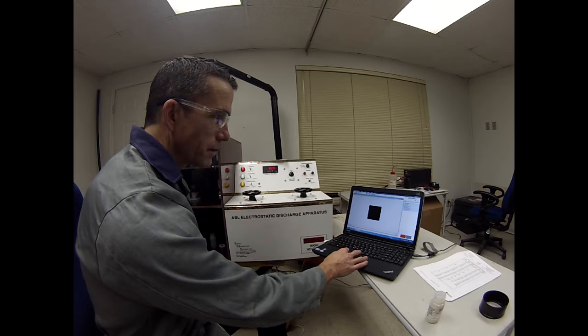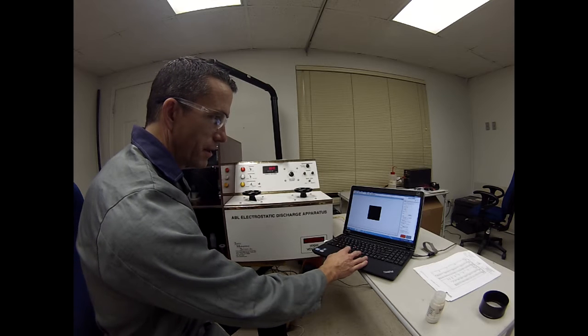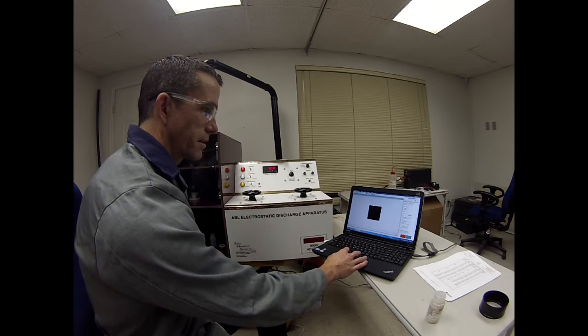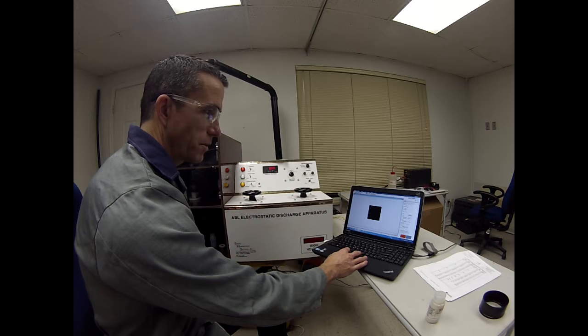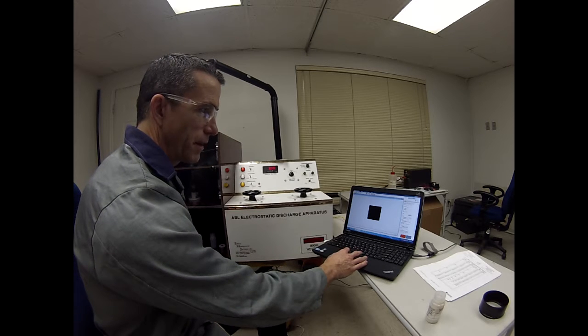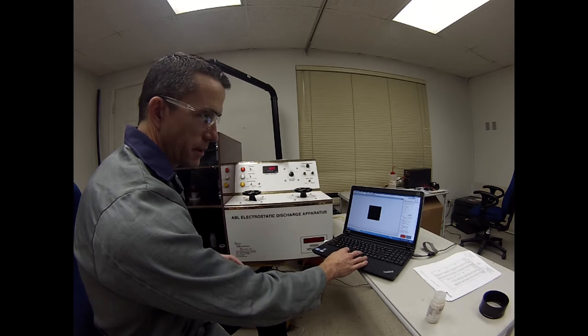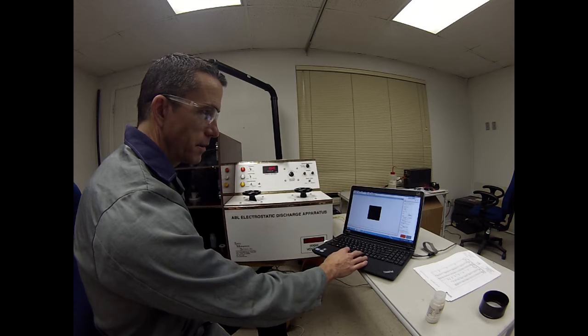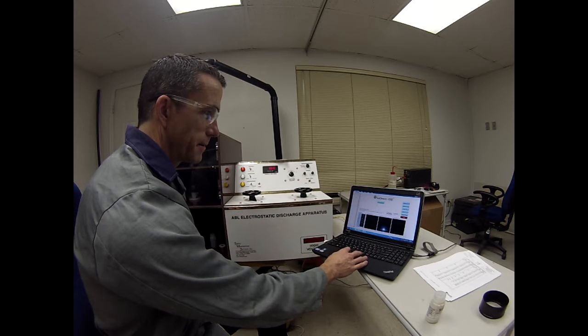I go to advanced settings, down to the trigger. It was on rising edge with a filter time of 0. So it can be on falling edge as well and work, and with a filter time of 5 to 10. This particular time we used rising edge, 0 time. And this is what we got.